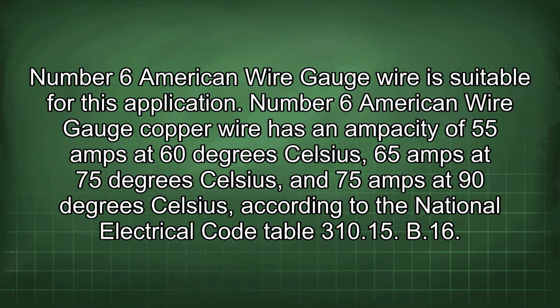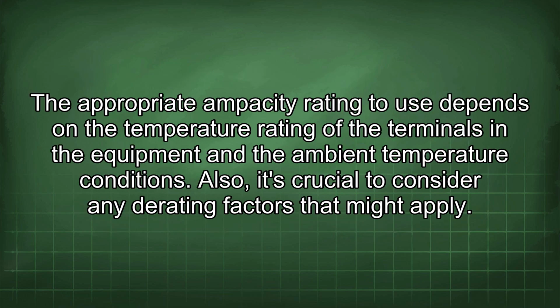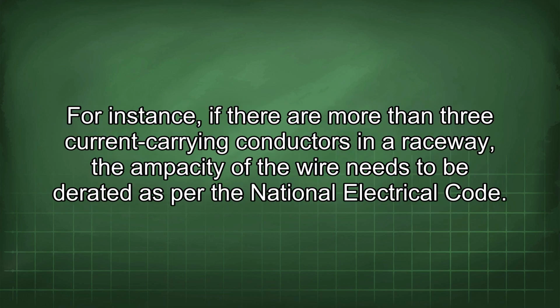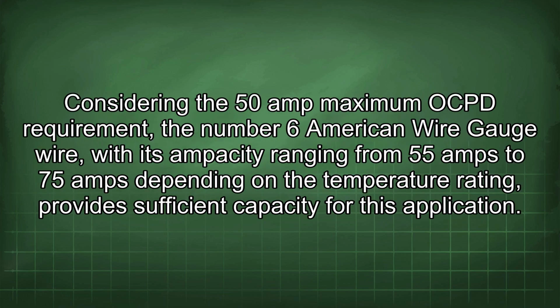The appropriate ampacity rating to use depends on the temperature rating of the terminals in the equipment and the ambient temperature conditions. Also, it's crucial to consider any derating factors that might apply. For instance, if there are more than 3 current carrying conductors in a raceway, the ampacity of the wire needs to be derated as per the National Electrical Code. Considering the 50 amp maximum OCPD requirement, the number 6 American wire gauge wire, with its ampacity ranging from 55 amps to 75 amps depending on the temperature rating, provides sufficient capacity for this application.